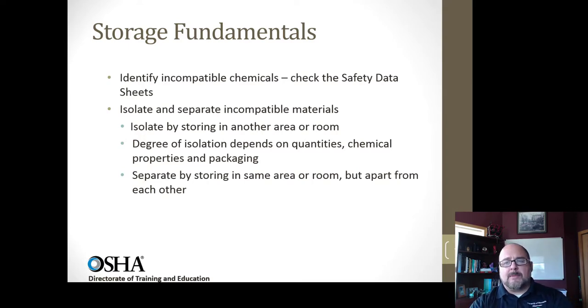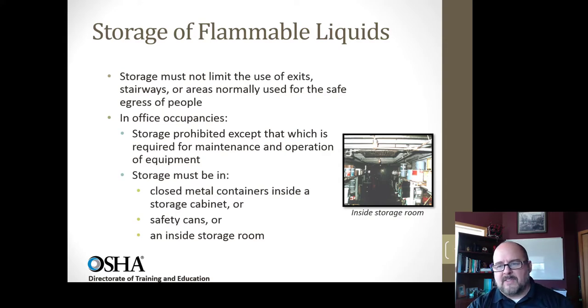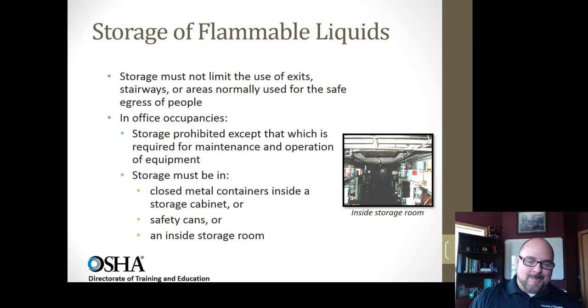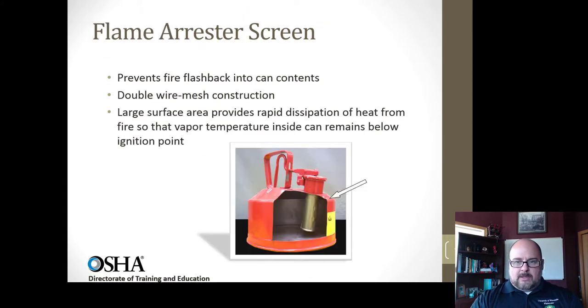Some storage fundamentals: containers should be labeled and you should have safety data sheets. I've got some products from my garage to show how you can find out what's in them. Keep flammable liquids in a cool, contained, or well-ventilated place. Storage must not limit the use of exits or stairways — keep them away from designated escape paths. Containers should be closed metal containers inside cabinets, or safety cans inside storage rooms. A safety can has a brass spark arrestor to prevent an ignition source from entering, and must not exceed five-gallon capacity per OSHA.